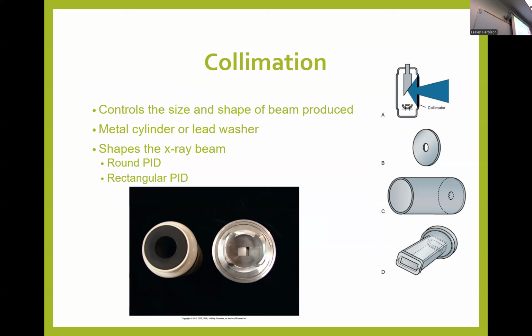So we have the aluminum filter, and then we have this diaphragm that's shaped like a donut, but this is made from lead. So don't get these two things confused. The aluminum filter covers the opening completely. All the X-ray photons have to go through the aluminum filter, and it filters out the weak ones. But now we have this lead collimator, at the same end as the aluminum filter.